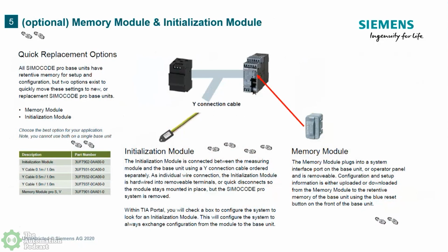Or our motor control center brethren, they have what we call an initialization module. That one is mechanically drilled into our wireways, so that if somebody racks out an MCC bucket and they rack in a new one, the initialization module, as soon as it sees power, it will dump the configuration into the SIMOCODE and they're up and running. And the key to that is that it's mechanically tied to that space. When it comes from our motor control center facility, it has a self-tapping screw that ties it into the hardware so nobody can walk away with it.